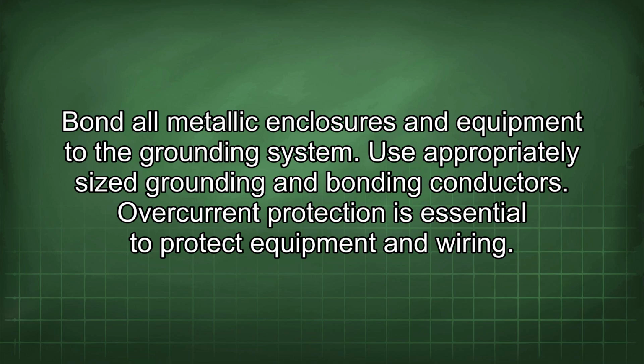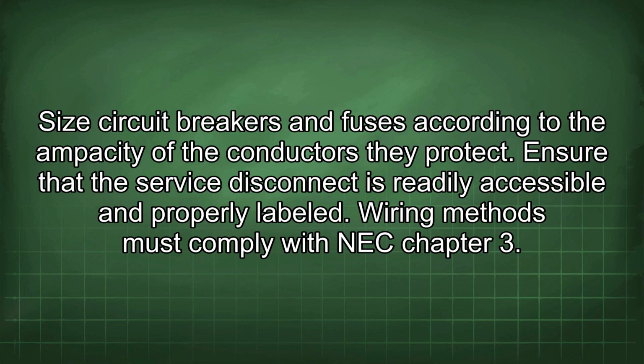Overcurrent protection is essential to protect equipment and wiring. Size circuit breakers and fuses according to the ampacity of the conductors they protect. Ensure that the service disconnect is readily accessible and properly labeled.